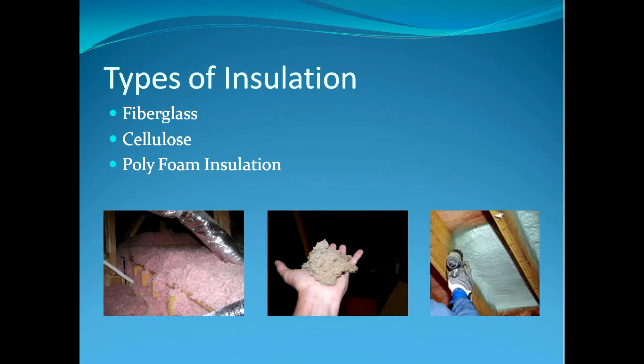Now, polyfoam insulations have superior R values. In fact, R values with polyfoam can be as high as R7 per inch. Polyfoams are also waterproof. Polyfoams can be exposed to large amounts of water constantly without any loss of R value. But polyfoams are flammable, and exposure to sunlight breaks down the foam, causing it to lose its integrity and R value as the sun turns the foam into fine dust over time.